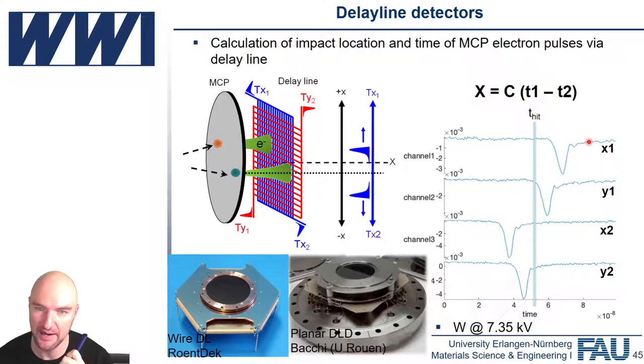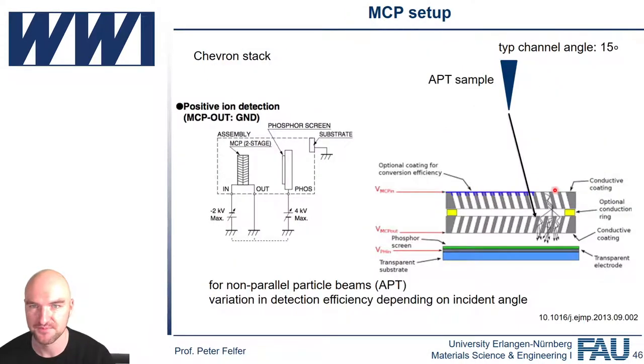We'll see later that in almost all modern atom probes, certainly the LEAP series, this information is not preserved. So what we get is we just get a time measurement from each of those channels. We don't know what the pulse looked like, if there were two together or whatever. This is information that is unfortunately lost. But I'm very positive that at some point we're going to have all of that information.